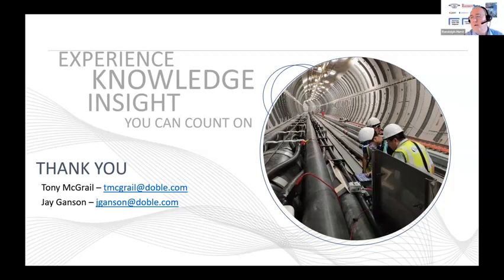What we have found over the years is that the larger voltage oil-filled cables are being replaced by cross-linked polyethylene. They did that, for example, around London in the UK, where there was a whole 400 kV oil-filled cable system, some of which went along canals, and they got replaced by polyethylene.